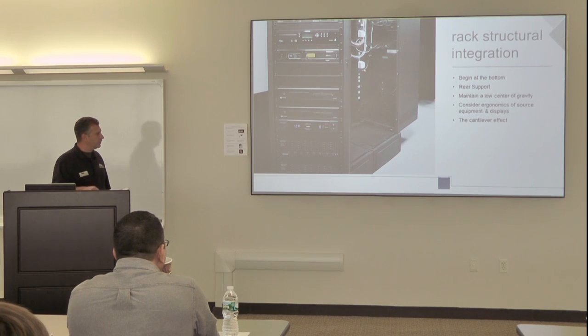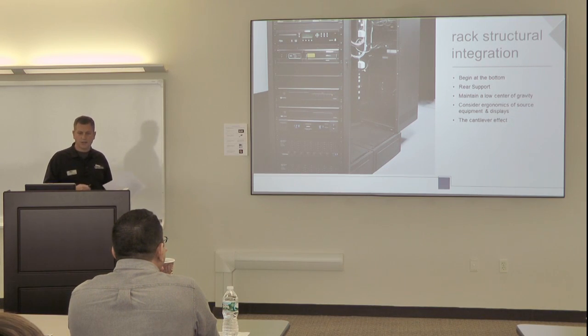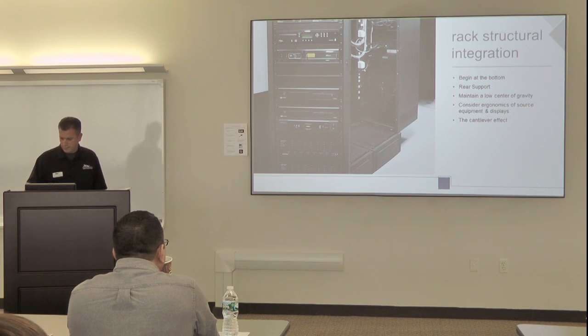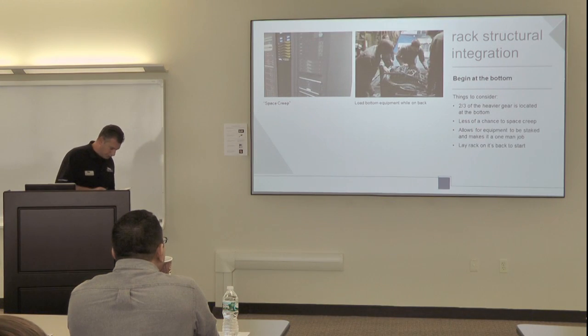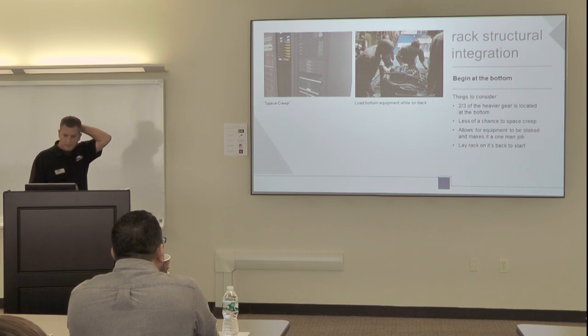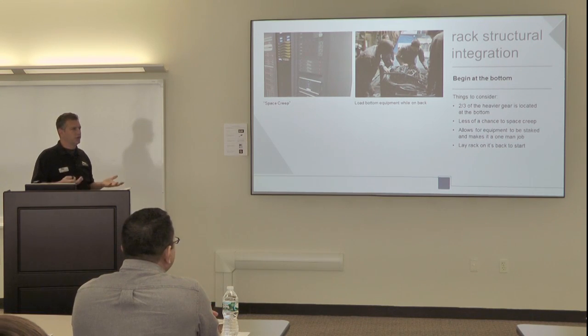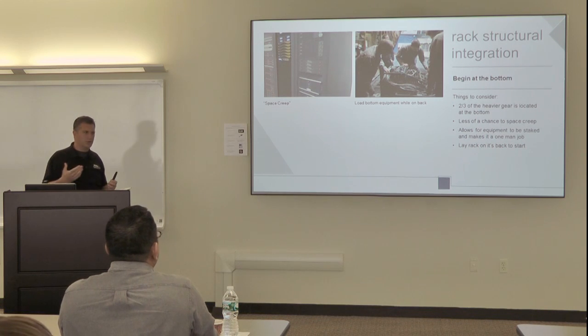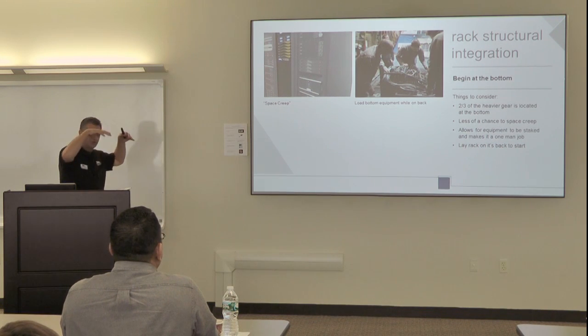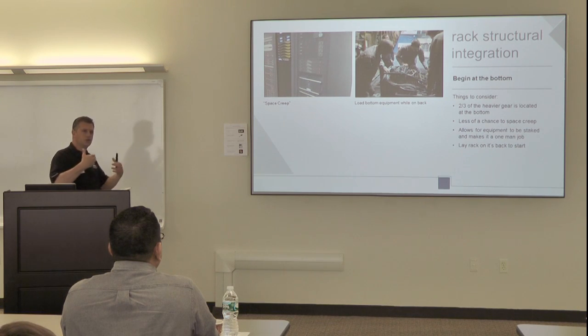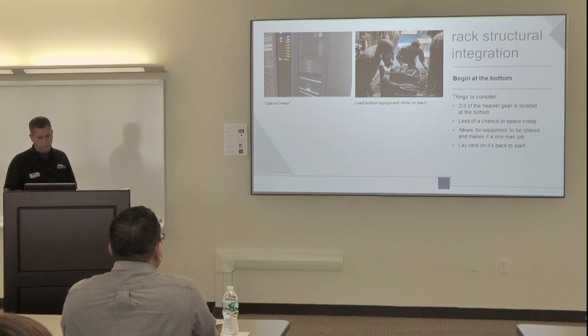Ergonomics, as well as the cantilever effect, matter for equipment that's not rear mounted. Beginning at the bottom, if you don't always have two guys to handle heavy stuff going into the rack, you can lay the gear down on its back and slide it into place. Even starting with just the bottom couple of heavy pieces, drop them in and that becomes your building block, so you're not holding equipment up while trying to get four rack screws in.